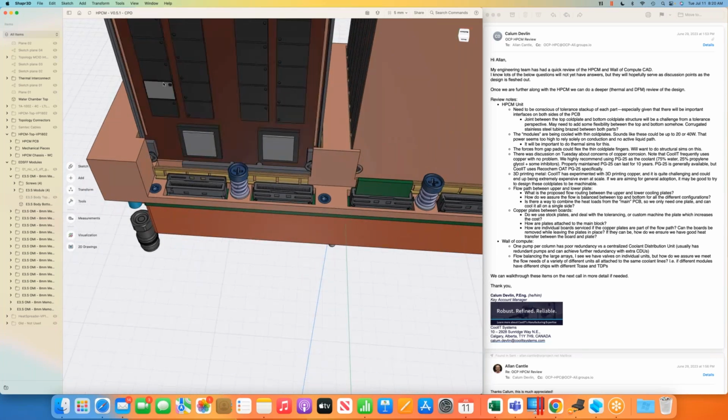I've got another smaller model of just a single module being plugged in. So that's what we're investigating there. There are some suggestions that we'd actually put water into these E3Ss, but I think that complicates things. We're trying to work with existing E3S technology rather than introduce water to them. These are in a region of 25 watts, which isn't too bad to cool, or 40 watts if we take a double width E3 and shrink it down to a single width. But the 40 watt budget is what the air cooled double width ones take, if that makes sense.